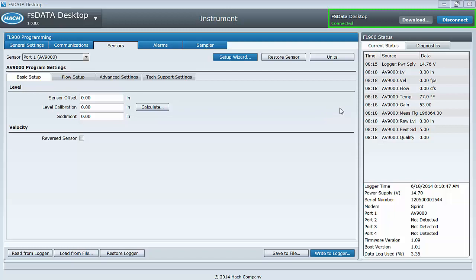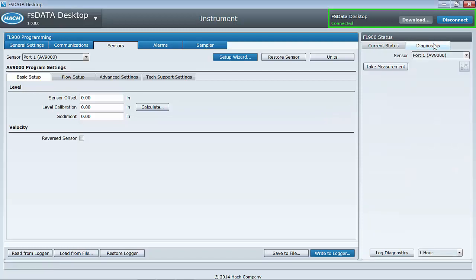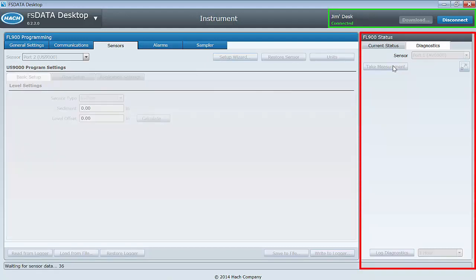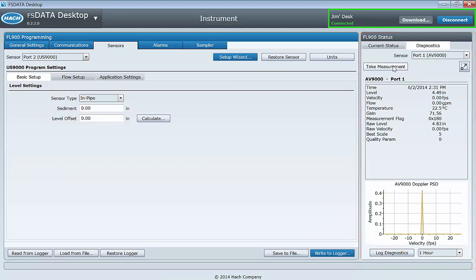It is best practice to verify the calibration at this point. To do so, select the Diagnostics tab here. Select the AV9000 sensor from the pull-down list if it isn't already selected. Left mouse click on the Take Measurement button. When the Take Measurement button is selected, it forces the sensor to take a measurement and display the results in the panel here. A successful measurement will look like this. Make sure the values populated make sense to you.